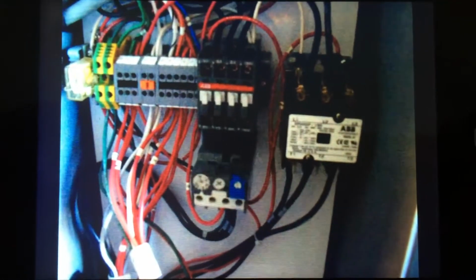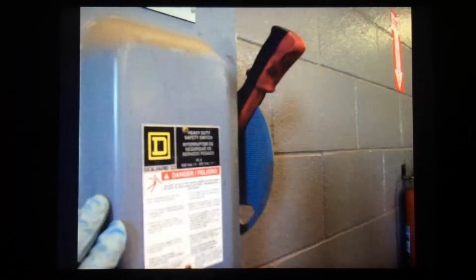We're going to continue our discussion on heating element testing and troubleshooting. We had talked about measuring voltage at the top of the contactor as well as at the bottom of the contactor whenever we're inside the cabinet, unless we're actually reading. Since my fingers are going to be in there, I'm going to go ahead and shut the safety disconnect down.